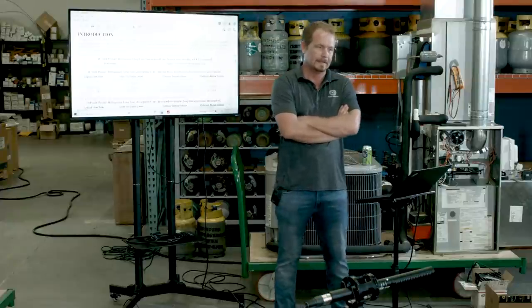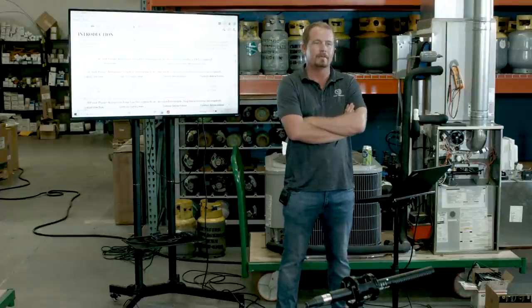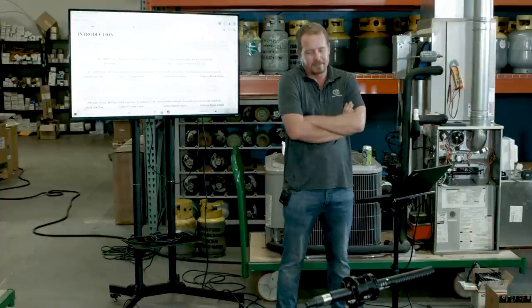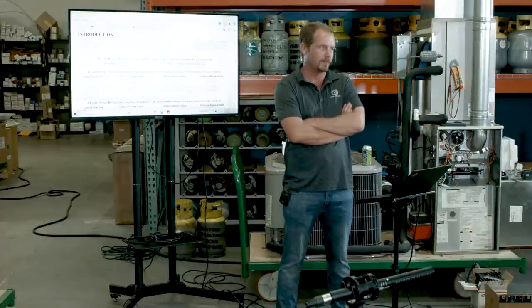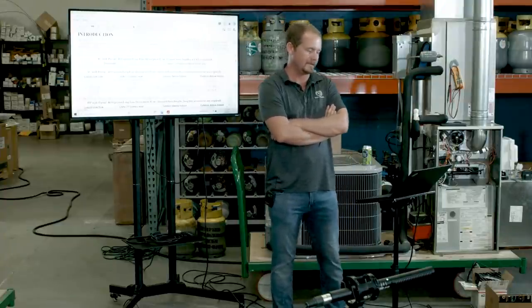Because we don't pay attention to the specs. Okay. And so it's easier for us, for two reasons. We don't pay attention to the specs, and it would be annoying to have to stock quarter inch liquid lines. But actually, if we have a short enough line length, and it depends on the tonnage of the system too, some allow it, some don't. You have to look at the specific product data for the system you're using.